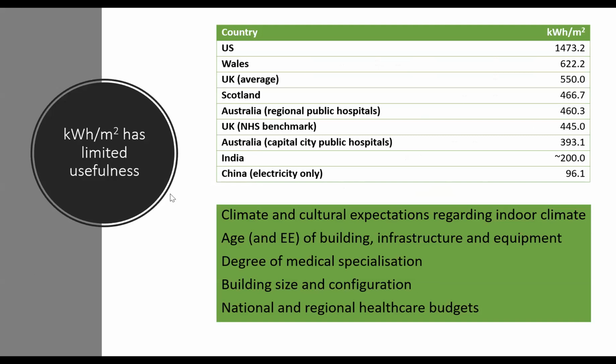These data show that kilowatt hours per square metre as a key performance indicator has limited usefulness. The table at the top is what we've gleaned from international research regarding the range of kilowatt hours per square metre from China up to the US in rank order, showing, for example, Australian regional hospitals at about 460 kilowatt hours per square metre, with capital city hospitals slightly less.